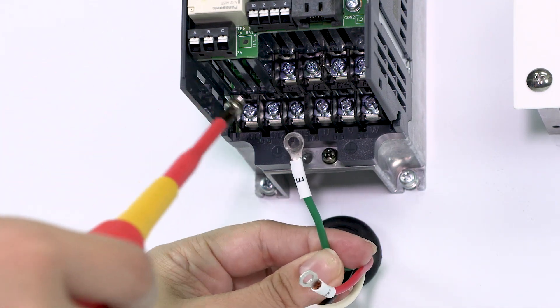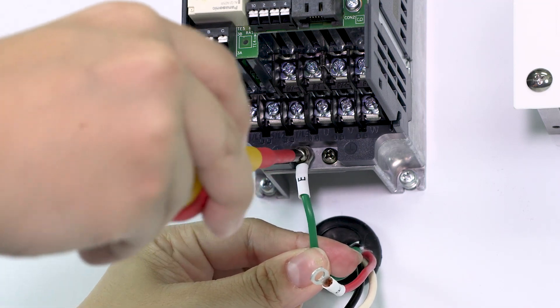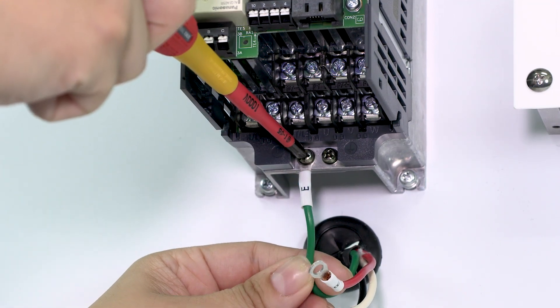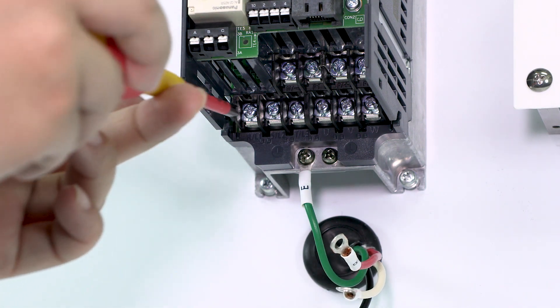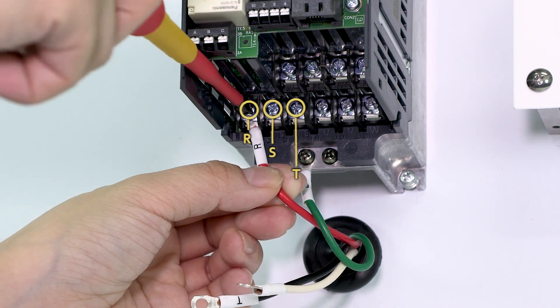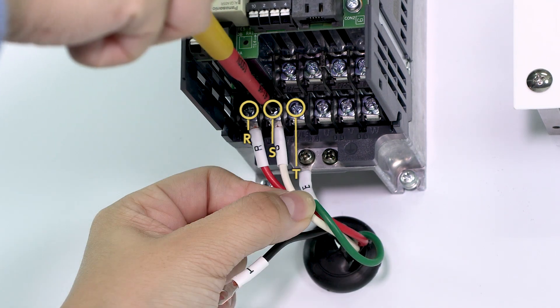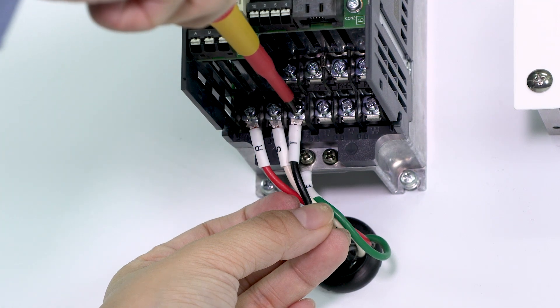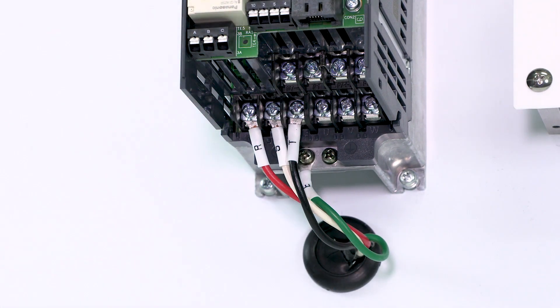First, attach the ground wire, then connect the power wires. Connect the power wires to terminals R, S, and T. Do not connect the power wires to the U, V, and W terminals, as this will damage the inverter.